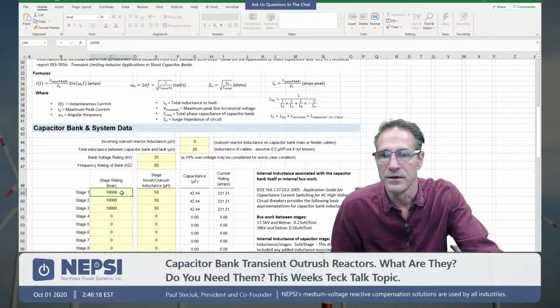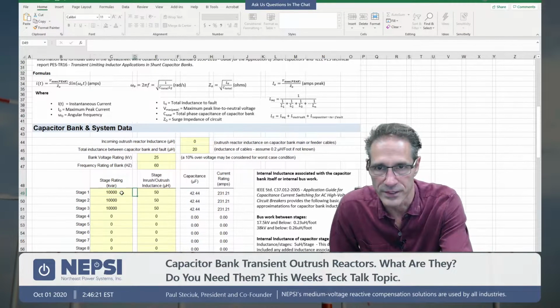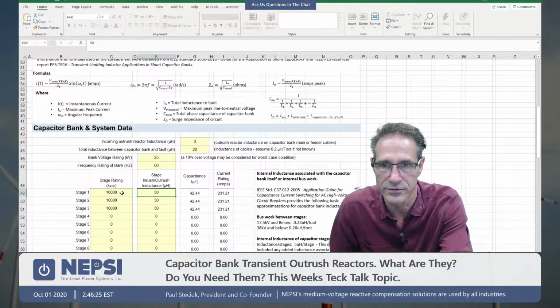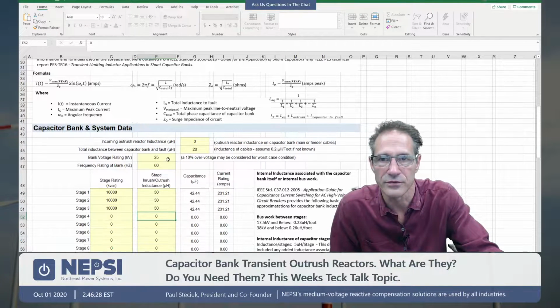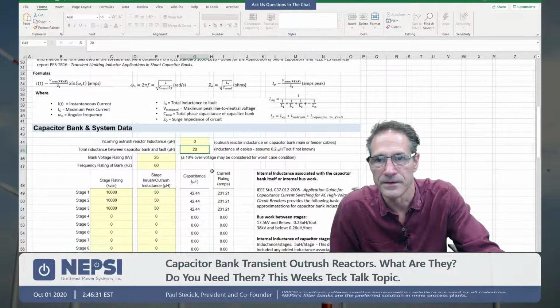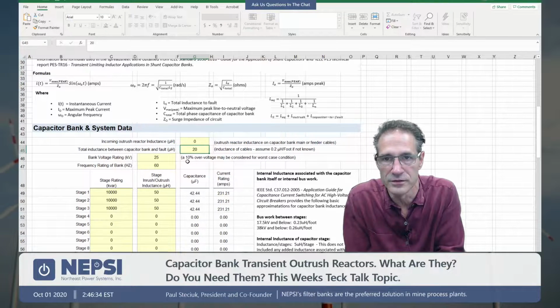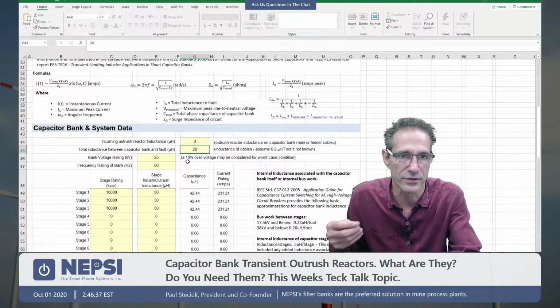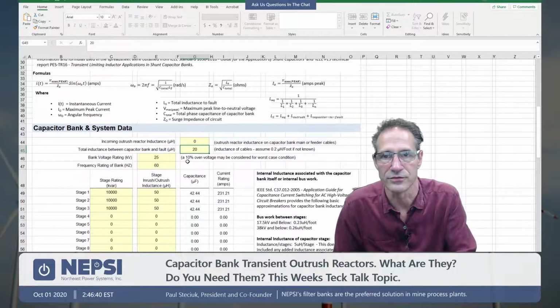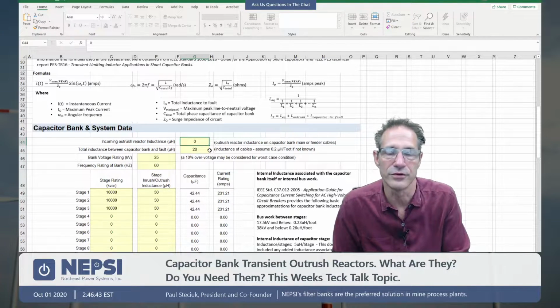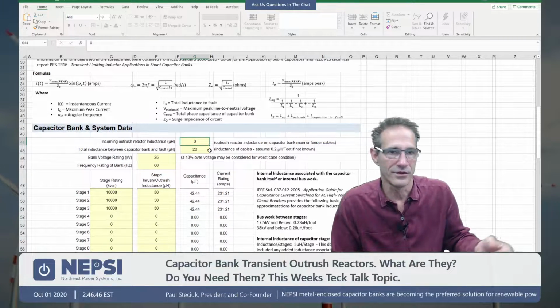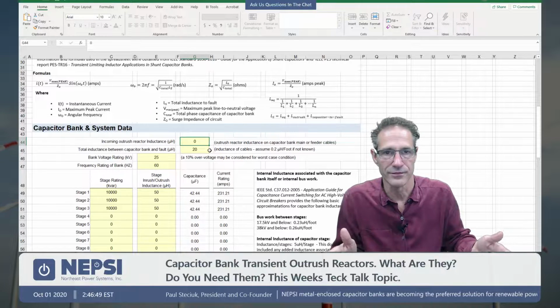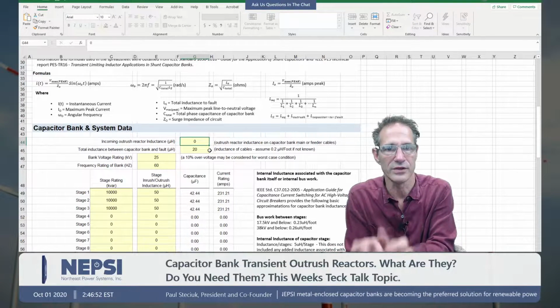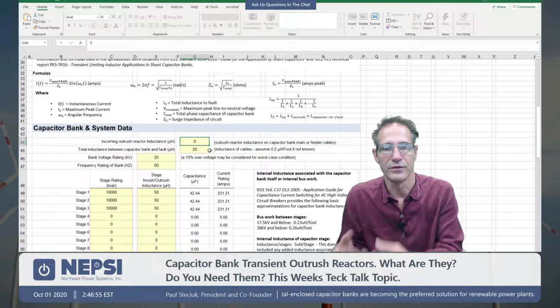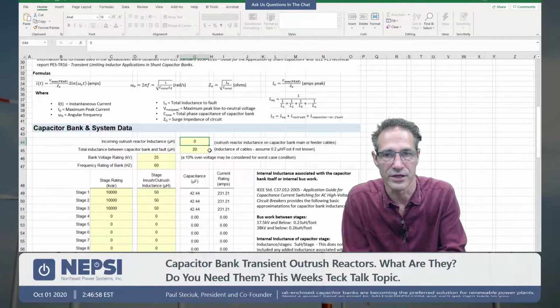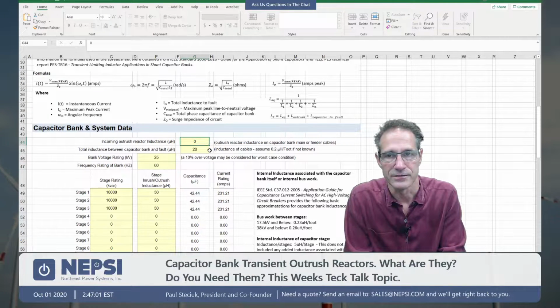System frequency, and then the kVAR of the bank, and then finally the actual transient inrush reactors. So in these spots here we have the transient inrush reactors, and over here we have the inductance between the fault and the capacitor bank. So basically that's the cable and the bus work, but it doesn't include the actual inductor itself. That is here. And if you think about what we're doing here, we're just adding the inductance up. Inductance from the fault point to the cap bank, in other words, the bus work and the cabling. Then we have the inductance associated with the outrush reactor, and then the inductance associated with each of the three transient inrush reactors. And they may or may not be present.